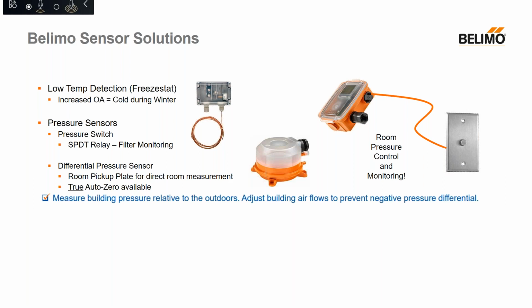Seeing that we're currently in a pandemic mode, every indoor facility really needs to be treated like a critical application. And for these types of environments, we offer what we call a true auto zero function on these sensors. Basically, this gives the sensors a self-calibrating feature that calibrates itself every 10 minutes, allowing the sensor to remain true and accurate to its original values. It really does give a set and forget type of feature here.